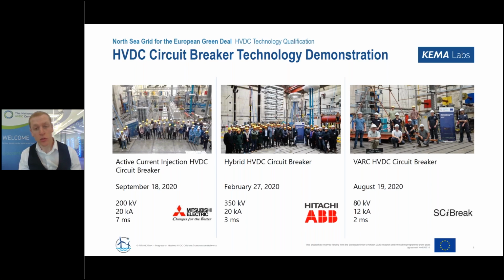the testing. So they were able to design test circuits in an existing AC power lab, which means that there was no major cost in erecting a dedicated DC lab. The trick was using the low frequency of the generators at 16 2/3 Hertz. And with this, all the critical phases of interruption could be replicated.